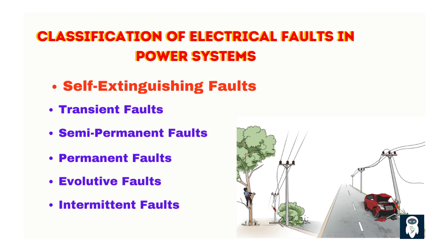Self-extinguishing faults are temporary by nature and naturally dissipate without intervention, typically within less than 100 milliseconds. They do not require the operation of protective devices or system resets. These faults are caused by transient external conditions, cause minimal or no damage to power system infrastructure, and are automatically cleared due to system stability or environmental factors. An example is wind-blown debris momentarily bridging conductors but removed by natural forces like gravity or wind.